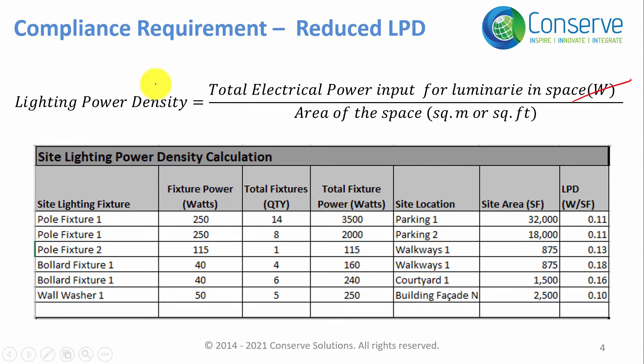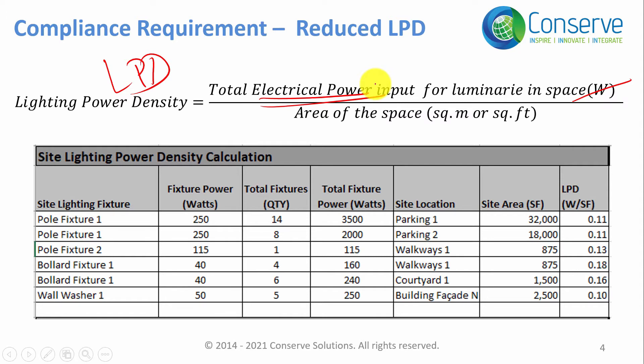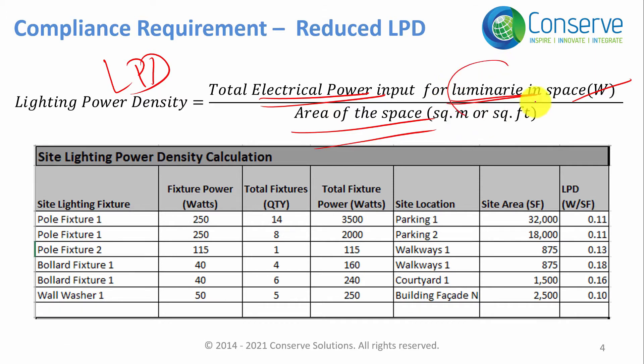Lighting Power Density (LPD) is the ratio of the total electrical power input for the luminaires installed in a space divided by the area of that space. Total electrical power is measured in watts, and area can be measured in square meters or square feet. A luminaire is simply a lighting fixture.